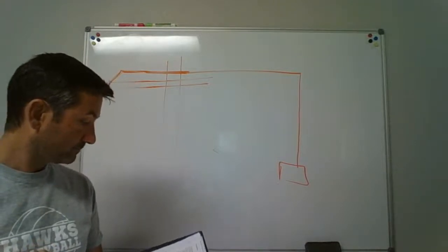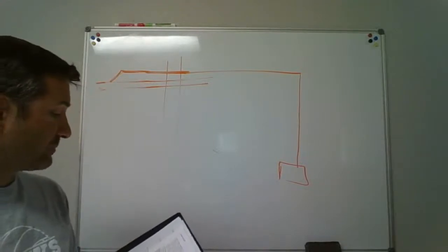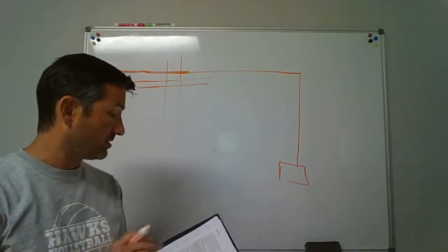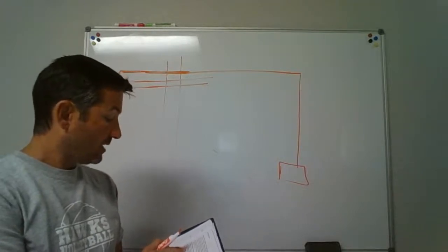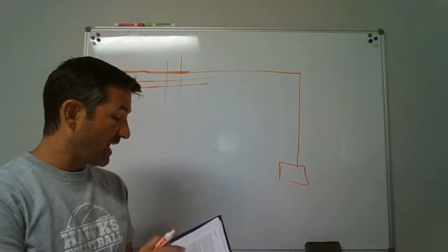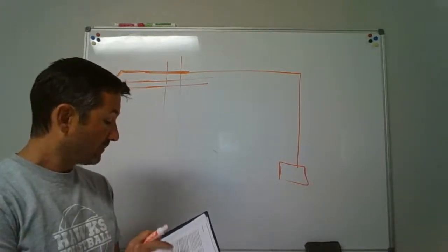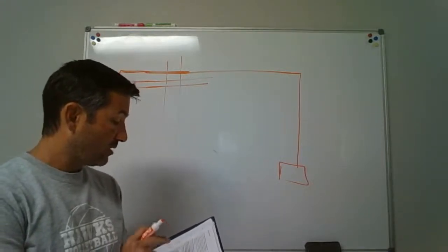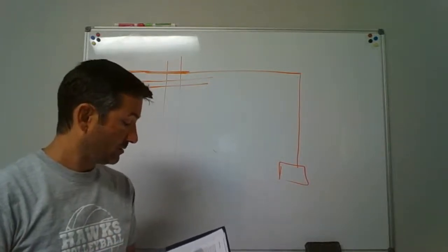Just so you know, with that one, it says the ejector pump discharge pipe shall not discharge directly into the septic tank. We can't just pop it into another hole in the septic tank. It says the pump line shall discharge laterally into a 4-inch gravity line, not less than 10 feet from the connection to the tank through a lateral Y branch. Okay. All right.